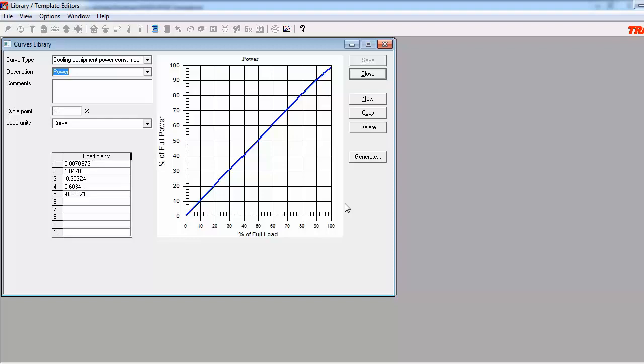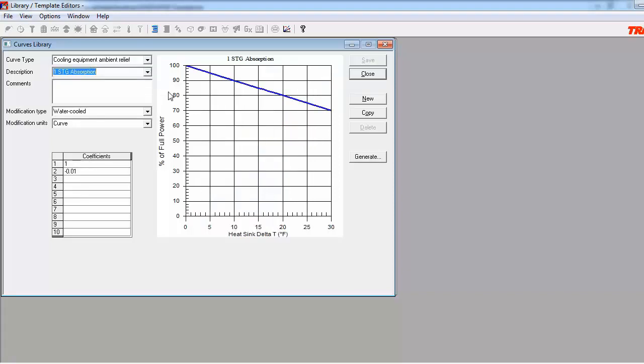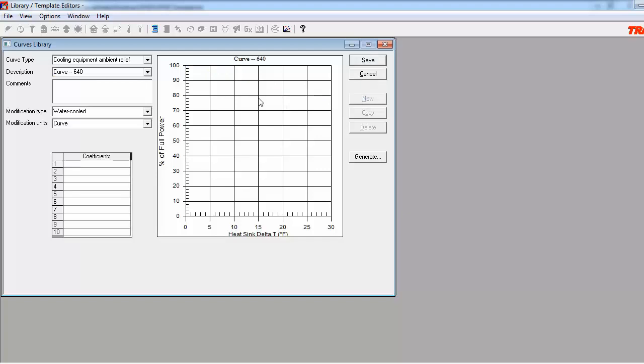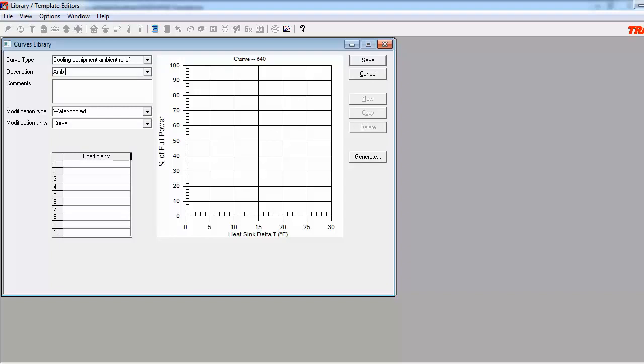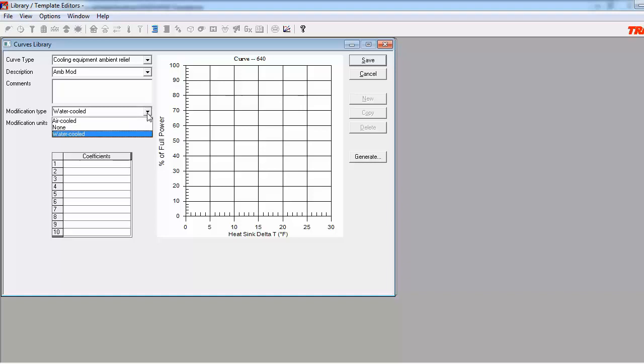Now we can move on to the Ambient Modification Curve. The steps used to create the Ambient Relief Curves are similar to those used to create the Power Consume Curves. There are a few added inputs though. After clicking on the New button, and giving the curve a new name, which we'll call it Amb Mod, and inputting some comments, we will need to specify the data that should be referenced for the Condenser Relief. To do this, use the Modification Type dropdown to select either Water Cooled or Air Cooled. Our selected equipment is Water Cooled, so we will select this option. We can now click on the Generate button.